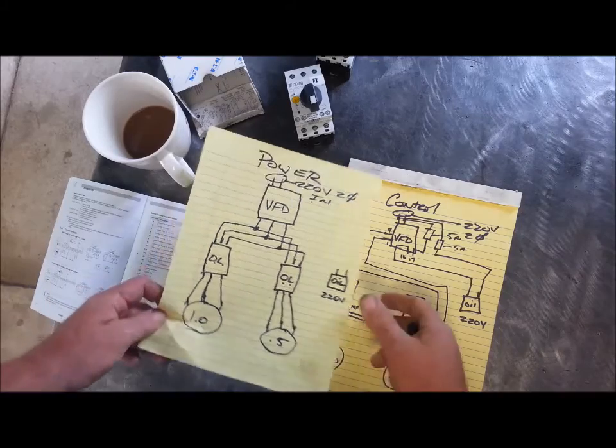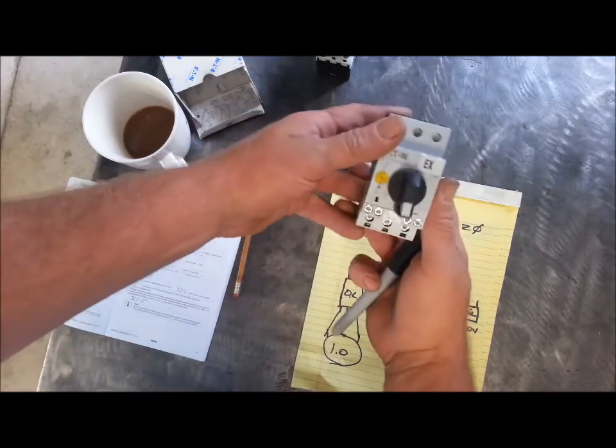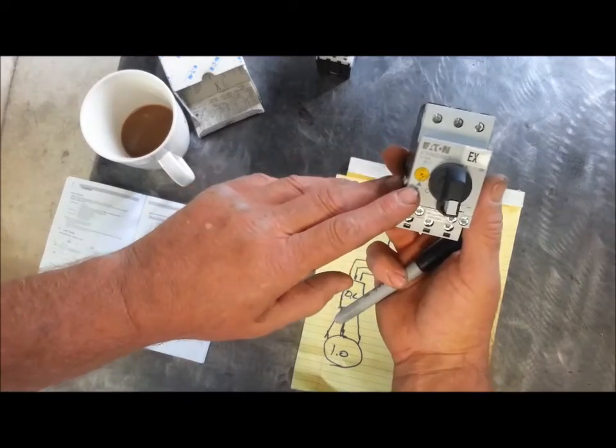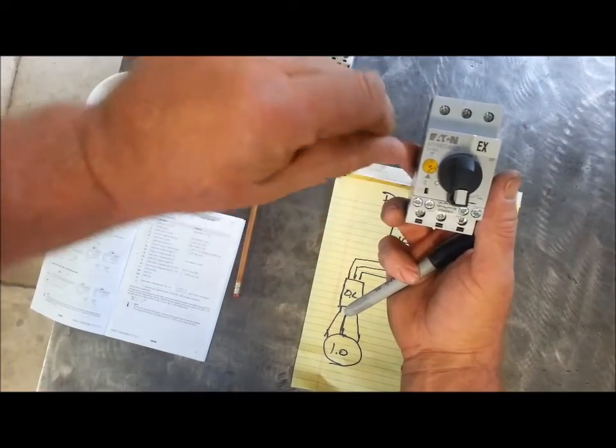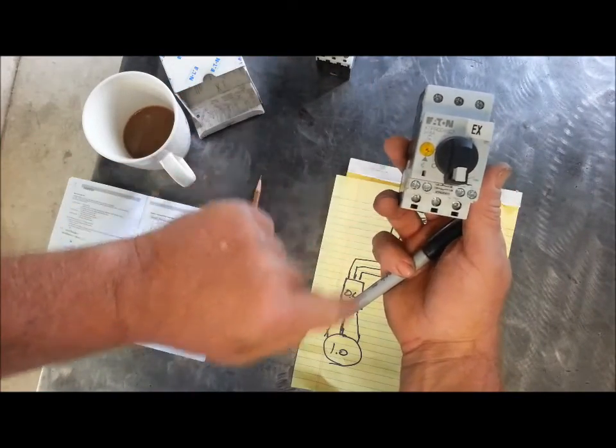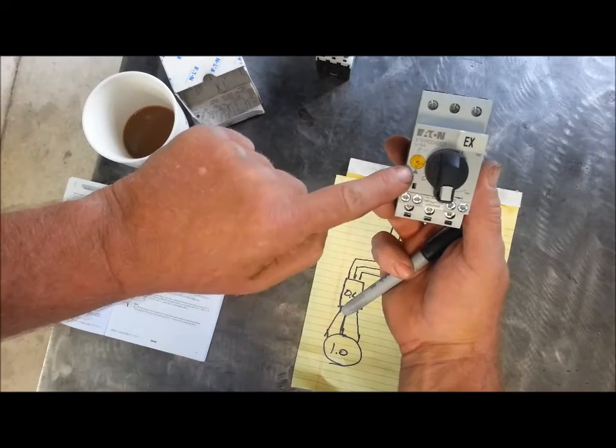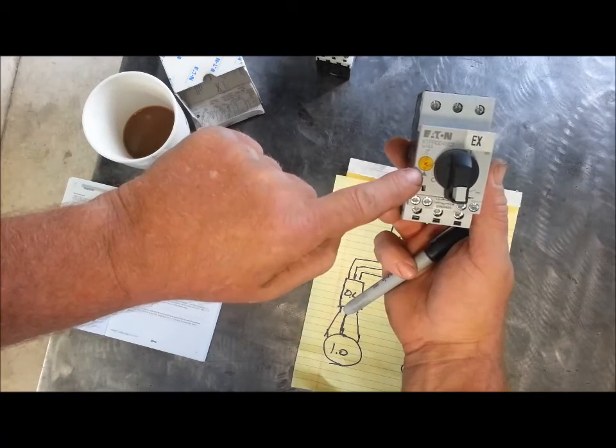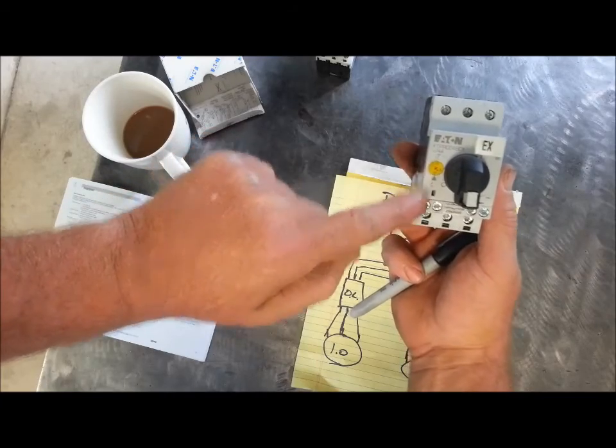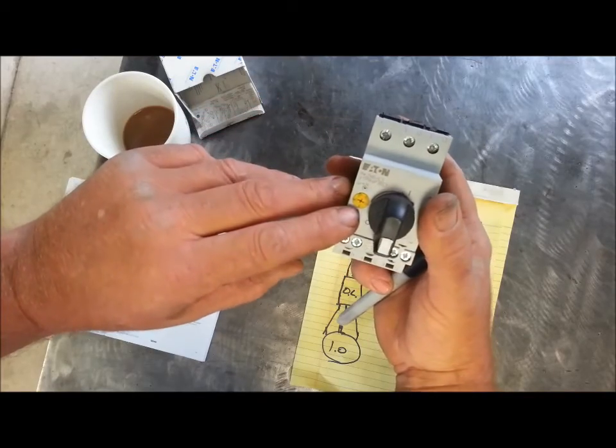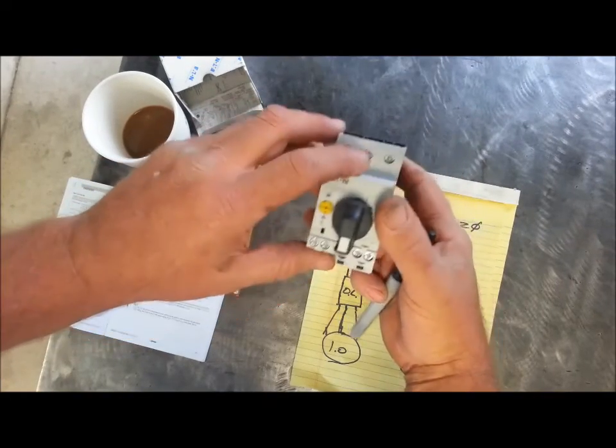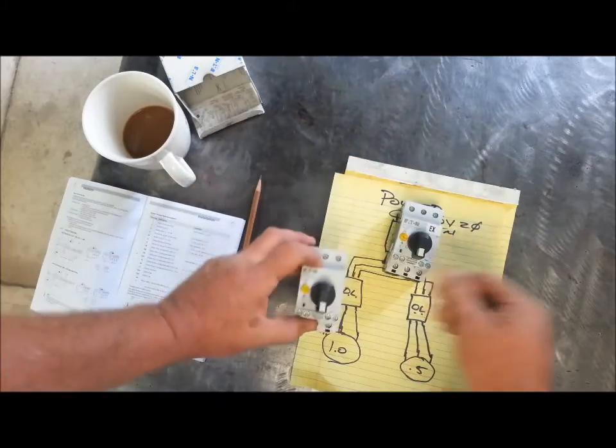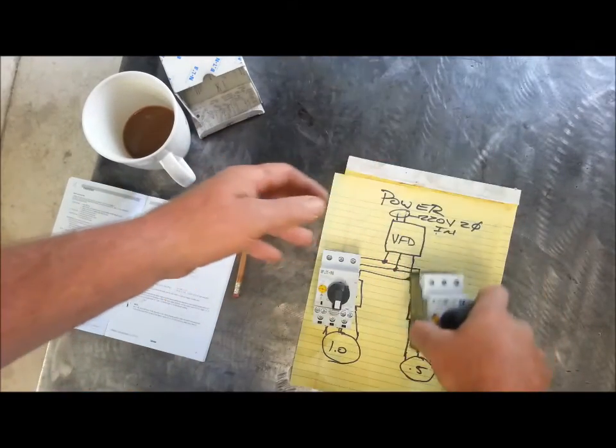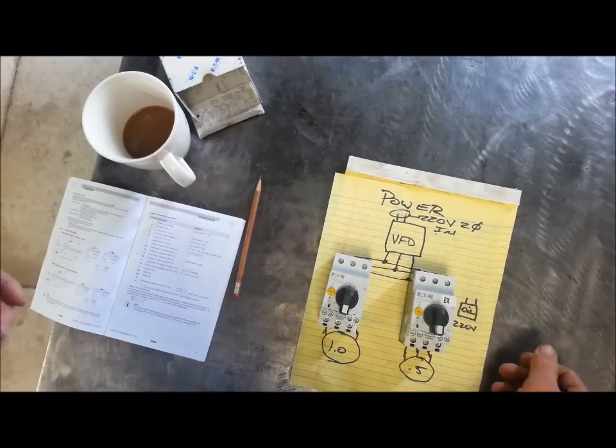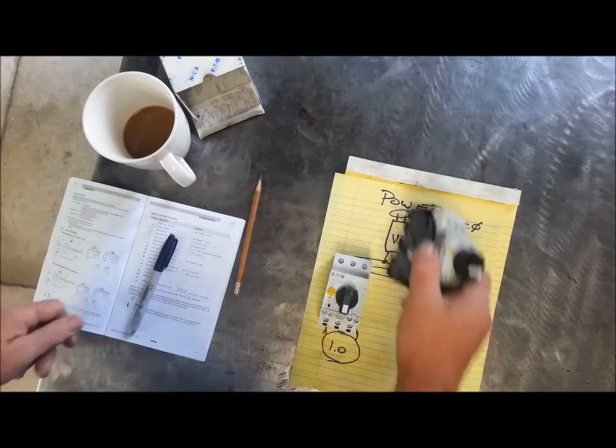The motors, typically, overload blocks are for running protection. This little yellow dial, you turn it based on your amperage draw of that particular motor. This one is capable of being adjusted from 2.5 to 4 amps. This one is capable of being adjusted from 4 amps to 6.3 amps. So this one goes on my one horse, and then this little guy goes on the little half horse. So those are the overload systems.